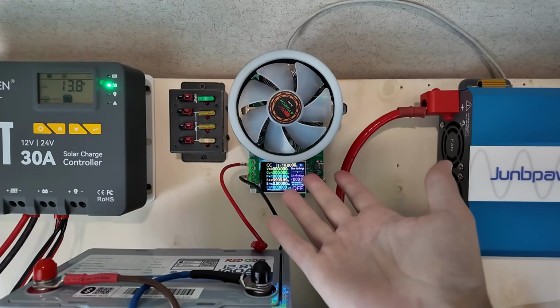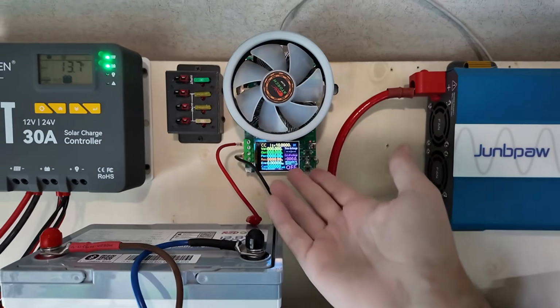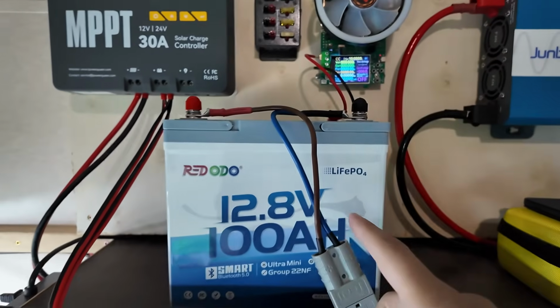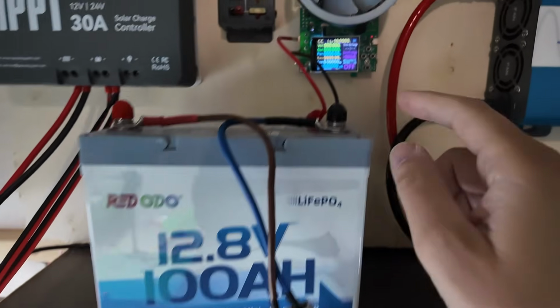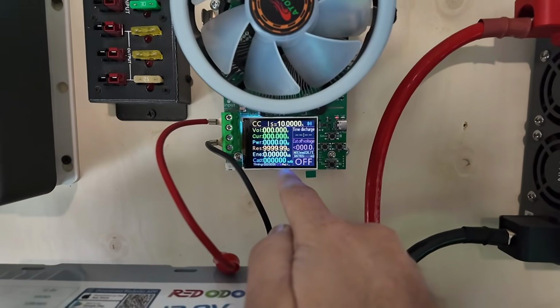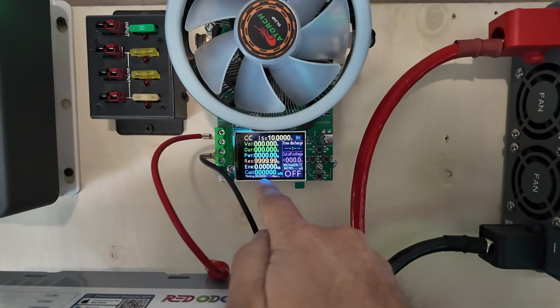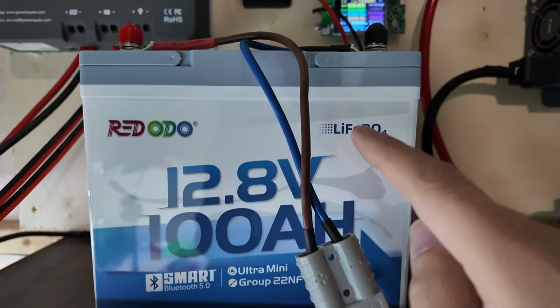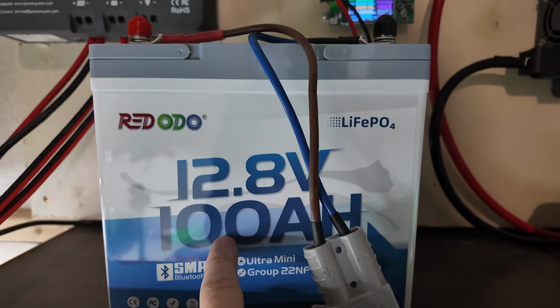This is a DC load device, and what we do is pull 10 amps continuously out of the battery until it is absolutely drained. At the bottom here there's a capacity reading, and it's going to tell me how much capacity is inside this battery—we're going to verify that it is, in fact, 100 amp hours.